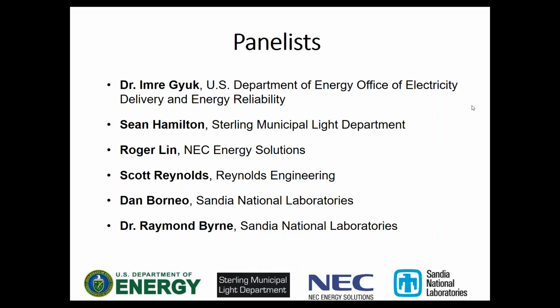I think we're looking at a storm where the system's down, the transmission's down. We've got PV, we've got batteries, we've got a control house. Could we get the three of them working together? You need a source side on your PV to operate. So once you get a line from your substation to your PV that sees the source side, it would operate like it normally does, backfeeding into the 13.8 system, which would then charge the batteries, which could then feed the police station. It would be a situation where everything is down, the system is out, transmission's down, and the three can be tied together. There'd be no other reason to take down any one of them.